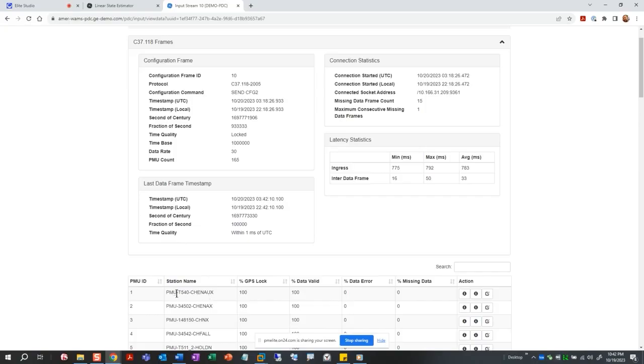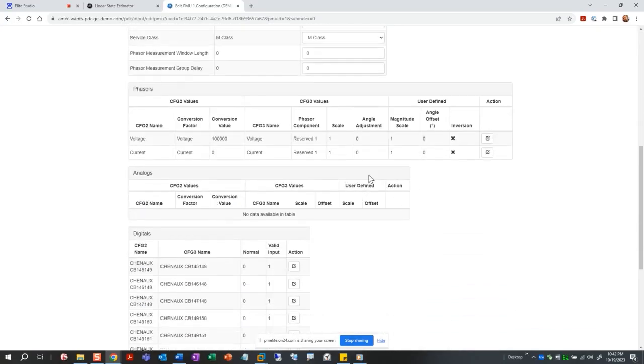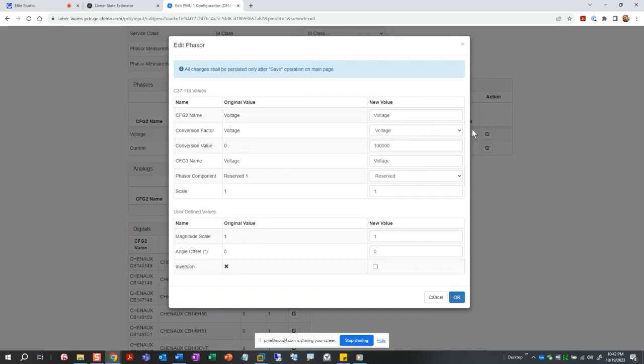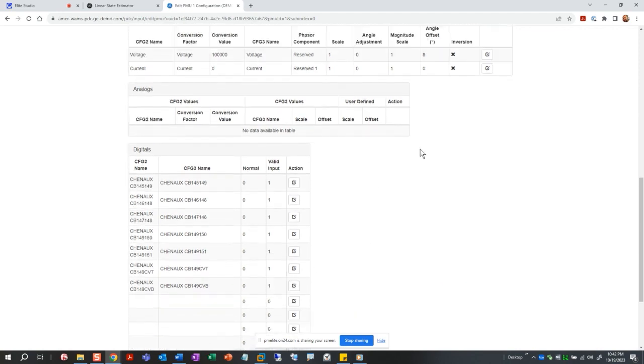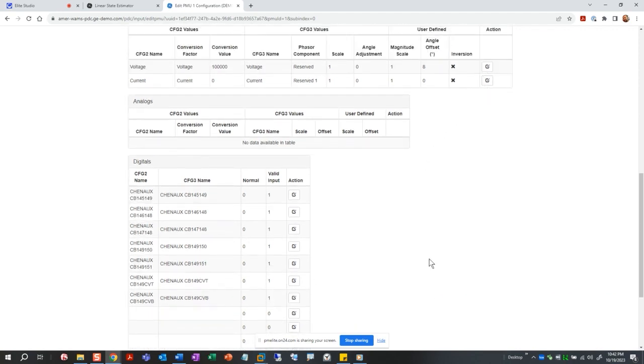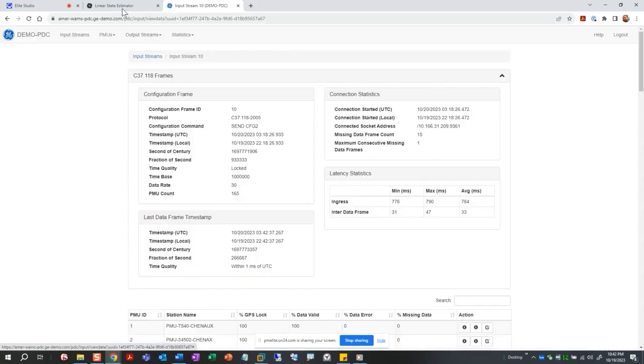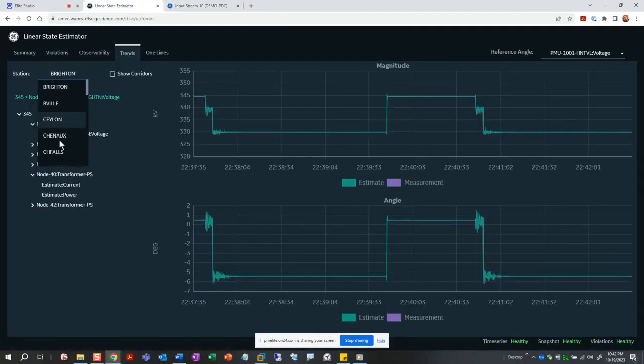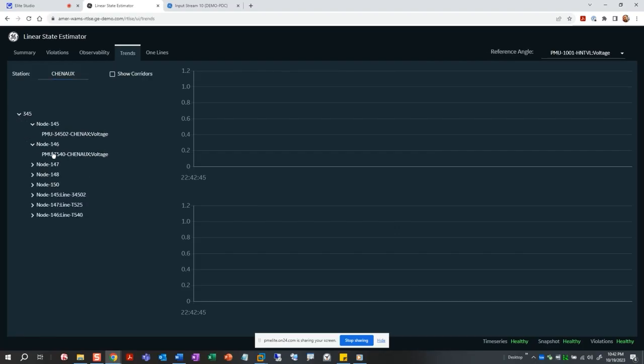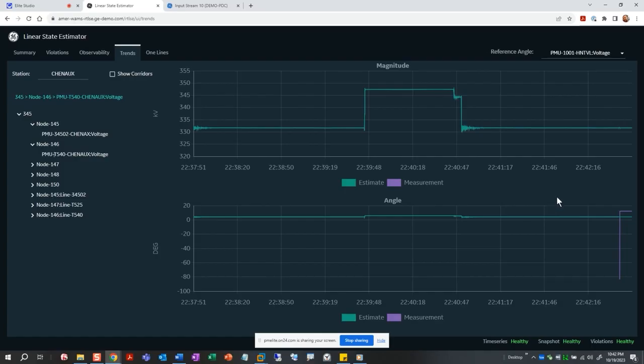So if I go to, let's go to Chenaux, this T540 PMU, I can go in and edit that. What I'm going to do is put in an angle adjustment on that. Let's say if I put an angle adjustment of 8 degrees and save that. So I was at Chenaux and my T540. So you'll see here that I've got my angle offset. So I put in an 8-degree offset, but my estimate is still in the appropriate alignment.